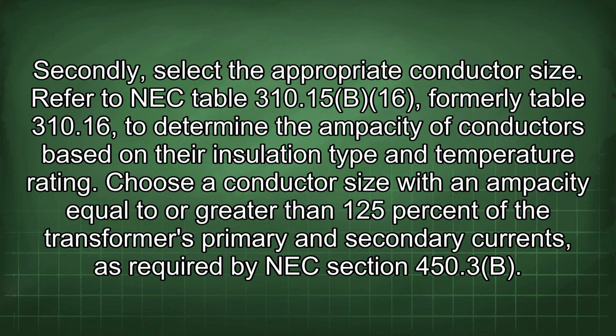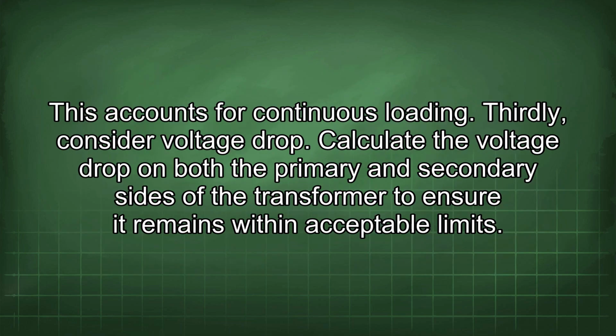Choose a conductor size with an ampacity equal to or greater than 125% of the transformer's primary and secondary currents, as required by NEC Section 450.3(B). This accounts for continuous loading.